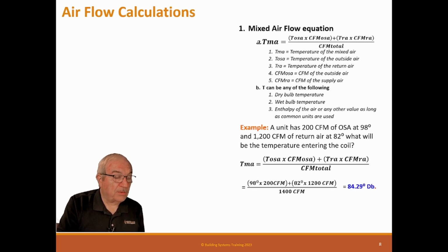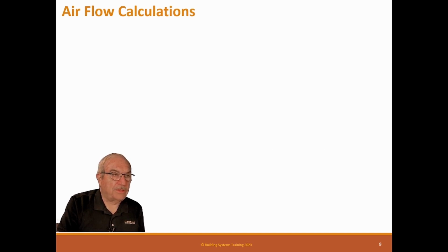So if we're trying to figure out what the temperature entering the coil is, we'll use a mixed air equation to do that. This is a really helpful equation, and you'll probably need to keep this in your memory instead of having to look it up when you need to know these temperatures.